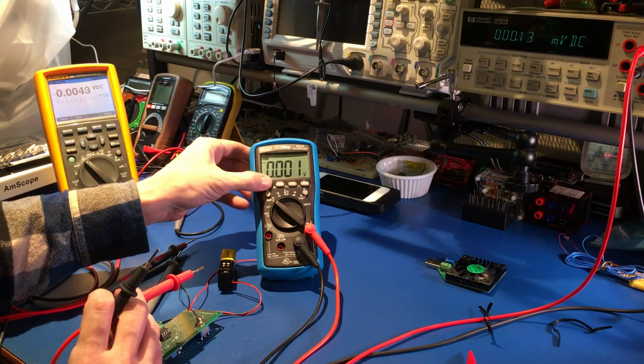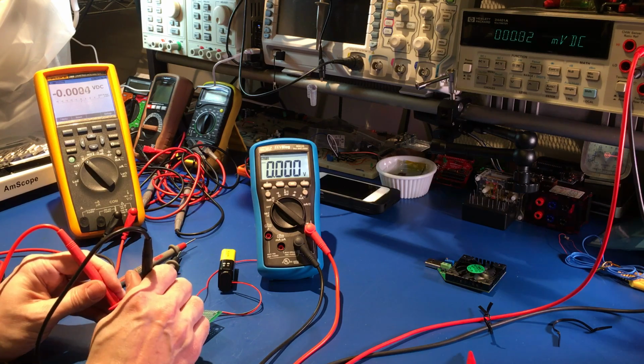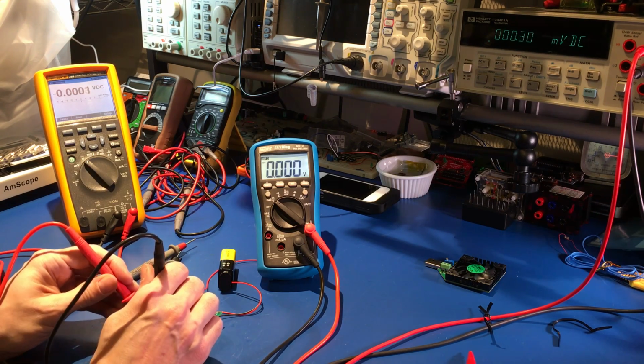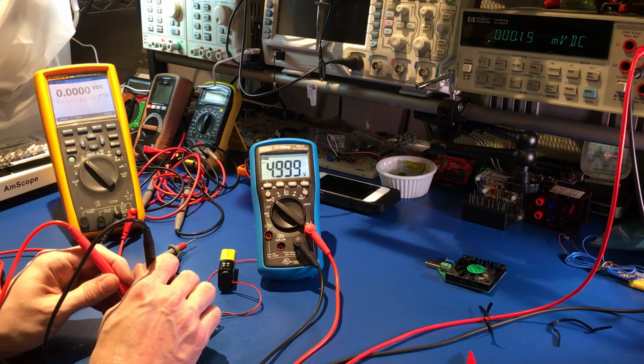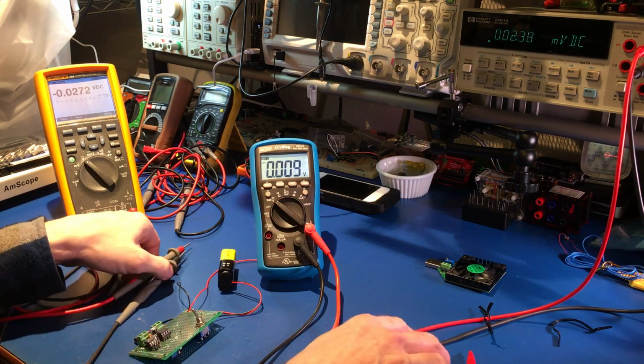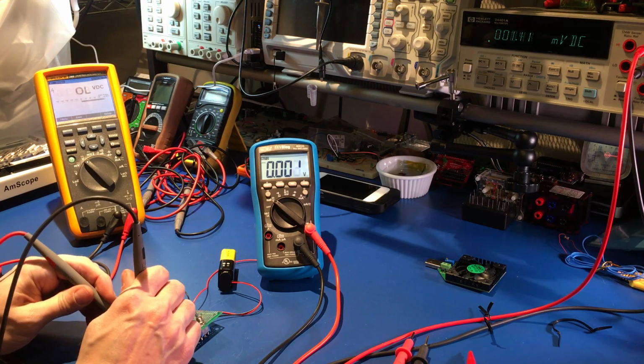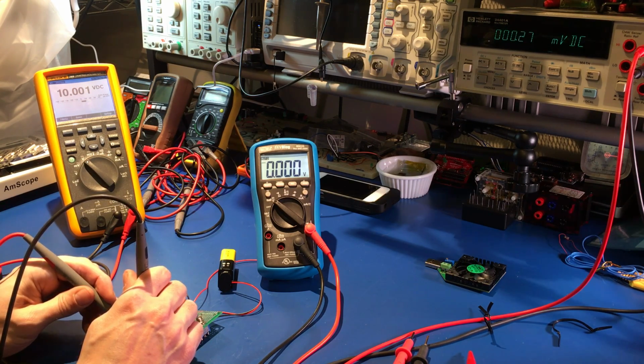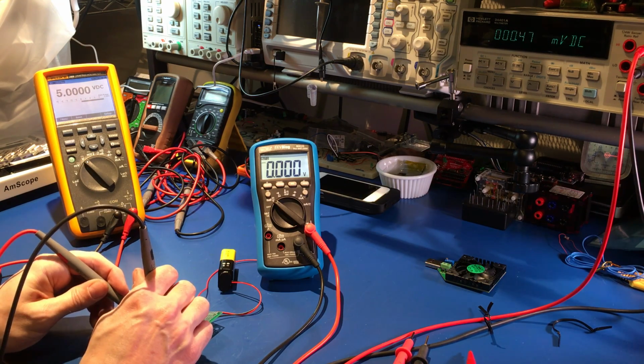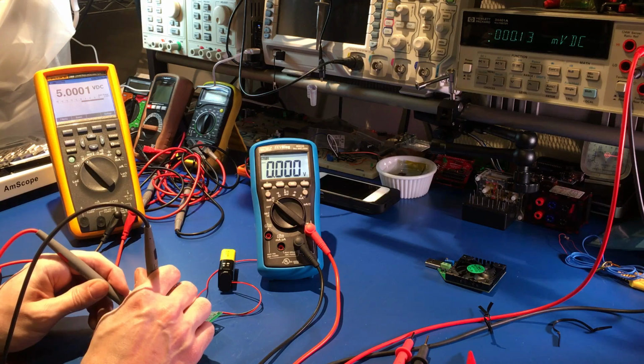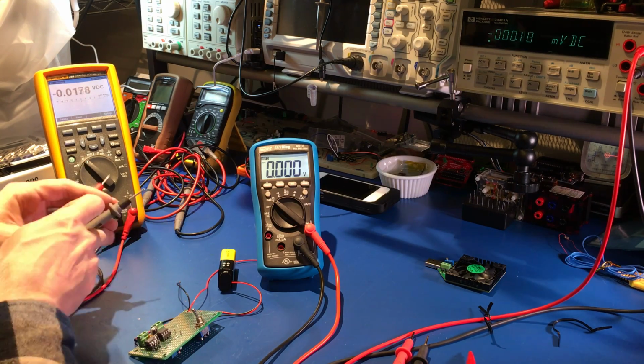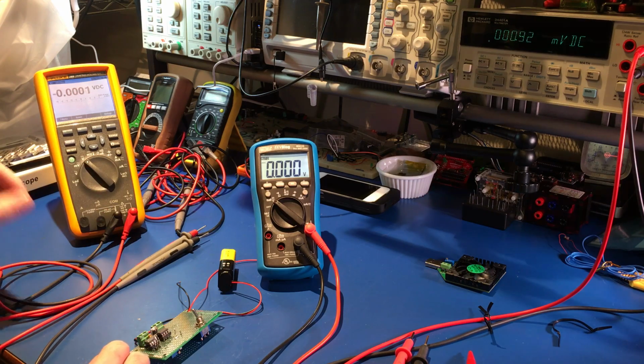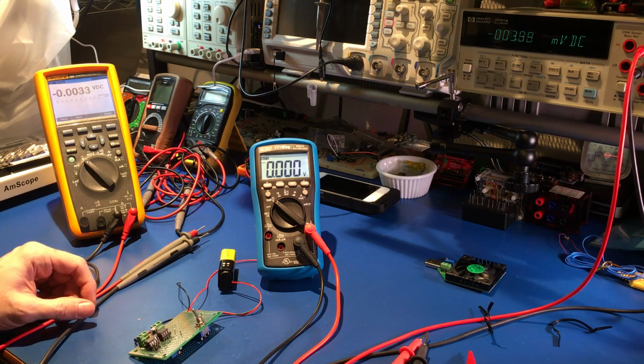Let's turn my light back on. And you can see I get the same reading here. And I get the same, close enough, definitely with the spec reading here. And let's go ahead and move over to the Fluke. And the Fluke shows 10.001, well within spec. And on the 5-volt range is 5.0001, actually 5.000, bang on, with the 1 being a flickering for the least significant digit there. Still cannot complain about that. Absolutely great accuracy. Everything matches up perfect there. No complaints.